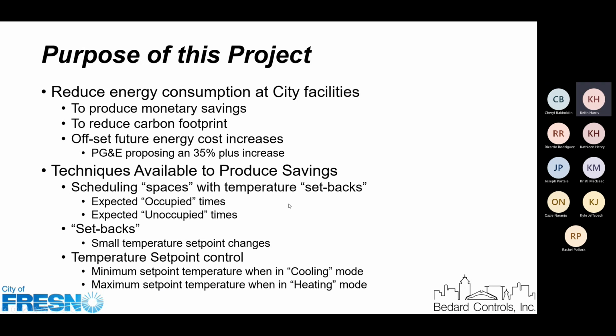The typical techniques to do that are, first of all, scheduling, trying to schedule the space to be occupied during times when people are going to be in the space, and then trying to schedule the space during unoccupied times. The second is setbacks. So we make a small temperature adjustment when it's unoccupied. Either we allow it to get a little warmer or we allow it to get a little cooler, but typically we don't turn off the equipment completely. We don't want the building to get too hot and we don't want the building to get too cold for freeze protection. So we just change the set point through the setback to a little less comfortable condition.